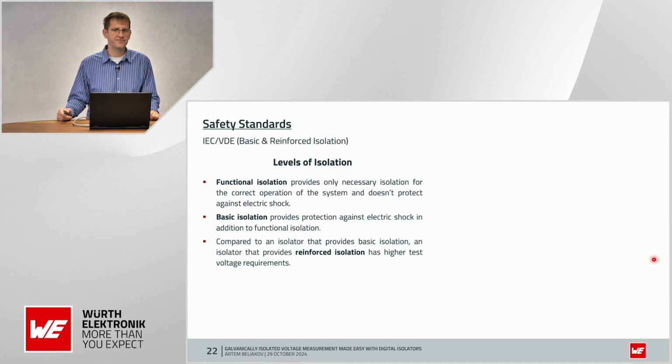First of all, of course, it's functional isolation, which provides only the isolation necessary for the correct operation of the system and doesn't protect against electric shock. Then, basic isolation provides protection against electric shock in addition to functional isolation.